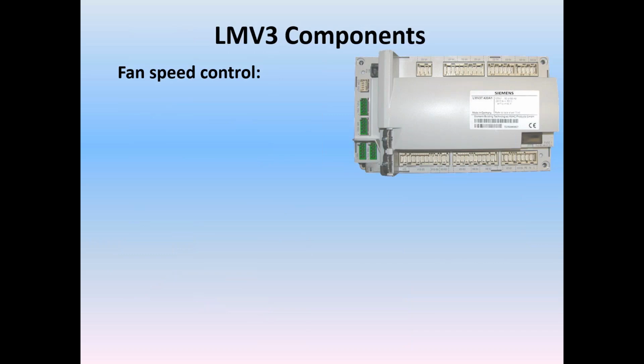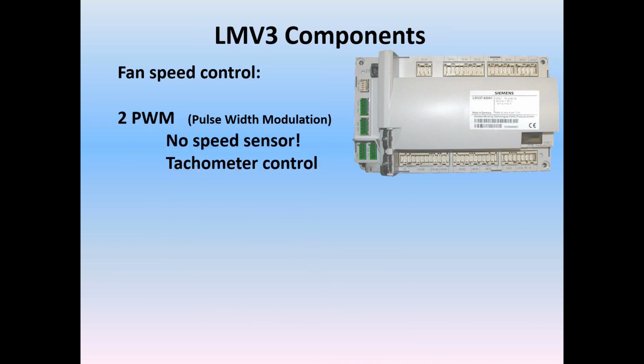The LMV3 also has fan speed option number 2, which would be the pulse width modulation, PWM controls. Pulse width modulation doesn't need a speed sensor. It has an electronic tachometer. The pulse width modulation motors can't turn backwards, so you don't need the asymmetric disc. They always go forward. They're DC brushless motors. And the tachometers are very accurate for the feedback for fuel-air ratio control.